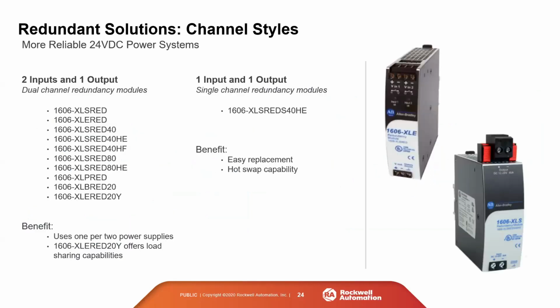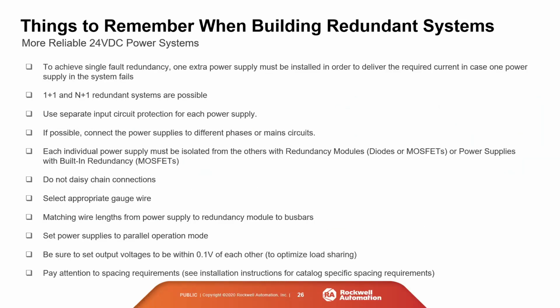We do offer our redundancy modules with dual channel and single channel. The only real benefit that the single channel has, that the dual channel does not, is that it's also hot swappable. So if that's important and you can get away with one channel, then that's a good feature. Just a quick checklist of things to remember when you are building a redundant system. Things like selecting the appropriate gauge wire.